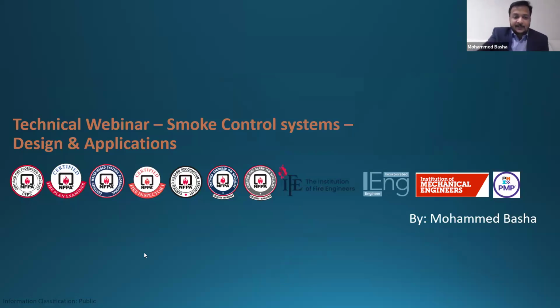Welcoming you all to the technical webinar on smoke control system design and applications. The main concept of having this smoke control system session for HVAC engineers who are members of ISHRAE is that the equipment for the smoke control system is often selected by mechanical engineers, not the fire and life safety engineers. The equipment, in the sense I'm referring to, means the fans, the location of the fans, the number of the fans, the capacity of the fans. So we would like to go into more technical detail to know the principles, the basics and understandings of the systems.